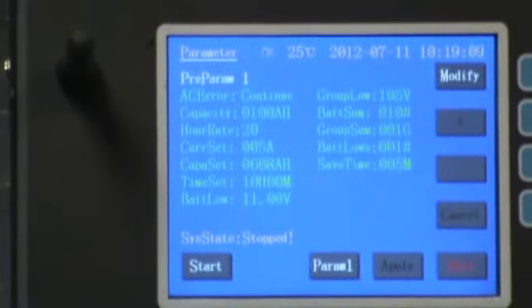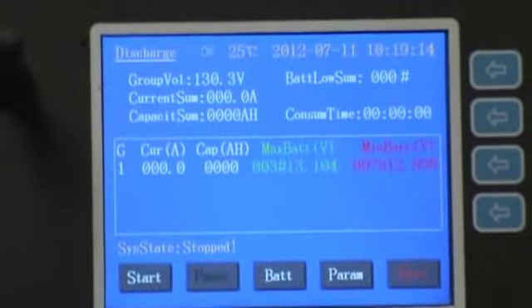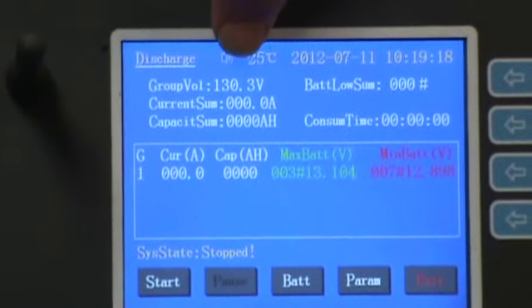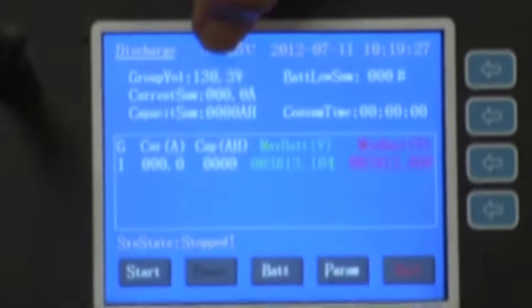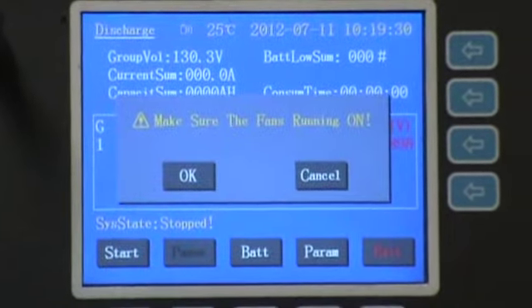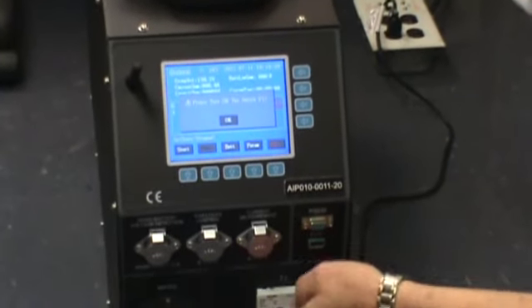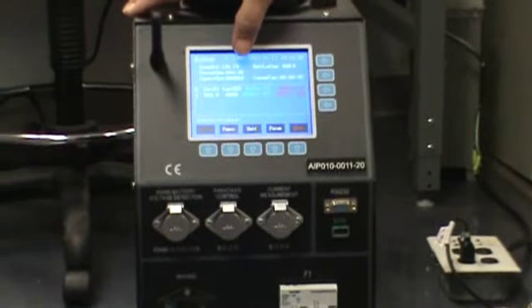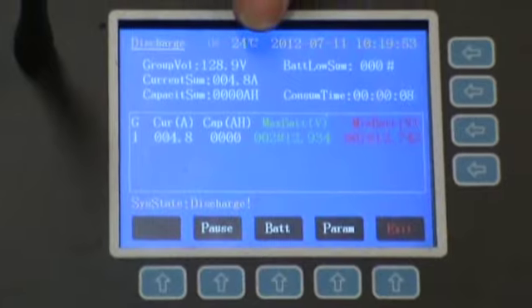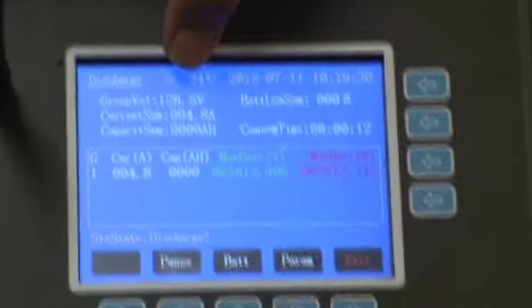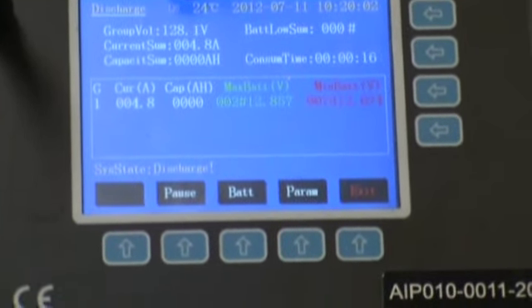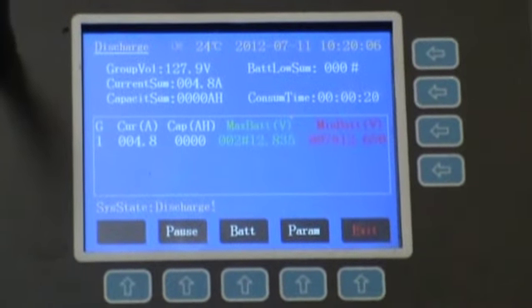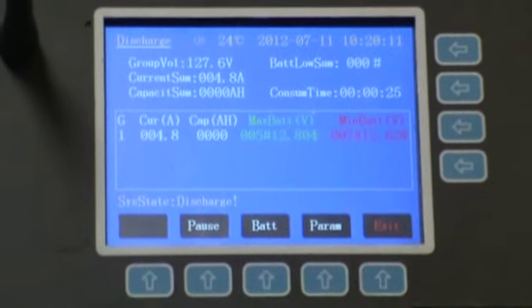Once you've selected the parameter, all you have to do is hit start. It gives you an idea of what's going on, and you'll notice it gives you the group voltage. It's already measuring the battery string for me, and it tells me the batteries are sitting here at 130.3 volts. I then hit start. It says make sure the fans are running. You say OK. It then says make sure you've got this circuit breaker turned on. OK. It then goes into its mode. It's now forcing 5 amps out of the batteries. You can also monitor the group voltage. At 5 amps, the batteries now drop down to 128.3 volts, and you can let it sit there and run for the hours that you've put into the unit. Now, I'm going to stop it.